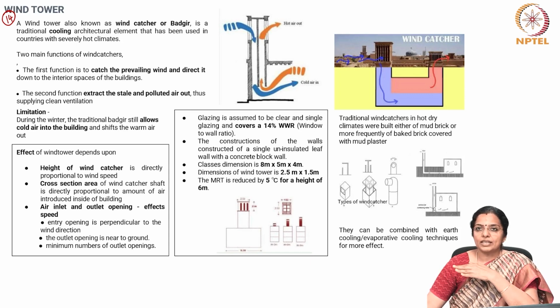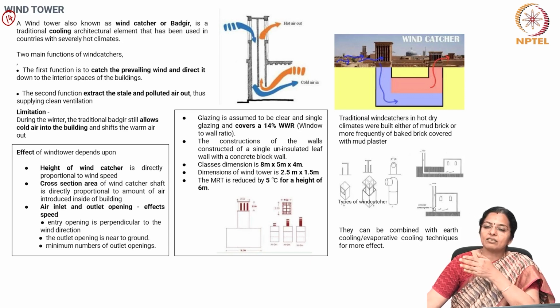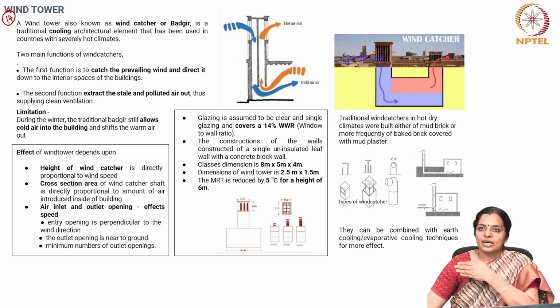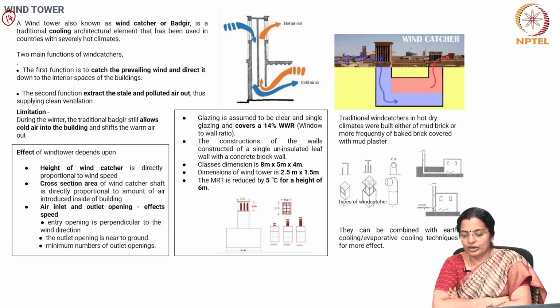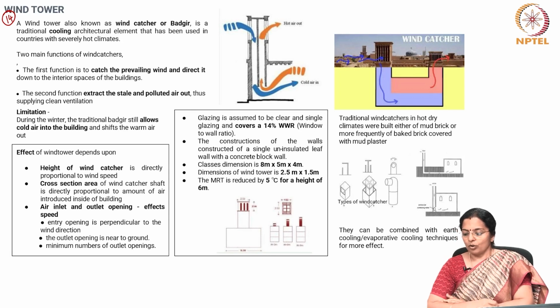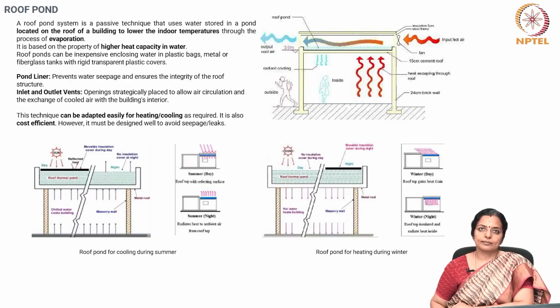Glazing is assumed to be clear and single glazing and covers about 14% window to wall ratio. The construction of the walls is single uninsulated leaf wall with concrete block wall. Traditional wind catchers in hot dry climates were built either of mud brick or more frequently of baked brick covered with mud plaster. They can be combined with earth cooling or evaporative cooling techniques for more effect.